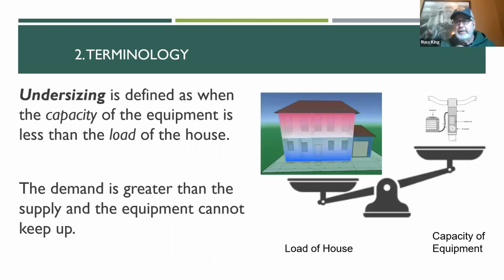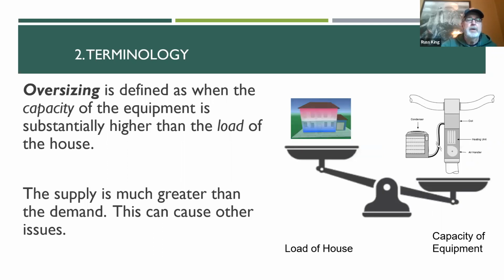So undersizing is a term you'll hear. Undersizing is defined as when the capacity of the equipment is less than the load of the house. So the equipment basically can't keep up. The demand is greater than the supply. And so that would be a situation where your heater was too small for the house on a really cold day. It just can't warm up the house. Okay. And the opposite is true for air conditioners.